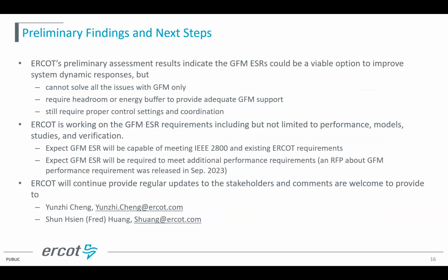So the conclusions basically summarize as follows. We plugged the model into our WECC test case, into the very big West Texas case, and also a small local ERCOT case. They all show benefits in terms of stability performance improvement. So it indicates that grid forming batteries could be a viable option to improve the system dynamic response. It probably cannot solve the issues with grid forming only, and it probably also requires some headroom and energy buffer to provide the support. It probably still requires proper control settings and coordination, but it basically shows some benefits. Right now we are working on the grid forming battery requirements, including the performance, models, studies, and verifications. That is our focus right now.